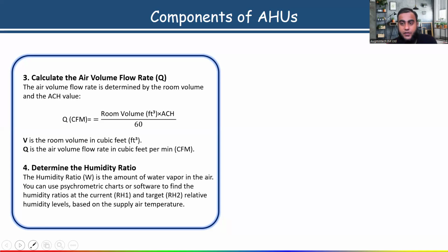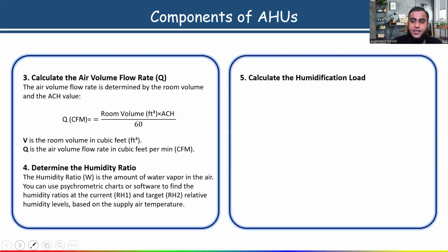So based on your current relative humidity and your desired, means targeted, relative humidity, we have to calculate the humidity ratio. Suppose your current relative humidity is 30%, for example, and the desired relative humidity is 50%. Now for both, as per your current relative humidity, you have to calculate the humidity ratio value from the psychrometric software, or if you have a chart, from there, and based on desired relative humidity, you have to calculate the humidity ratio value. Once you get this, now you can easily calculate the humidification load by using this formula.